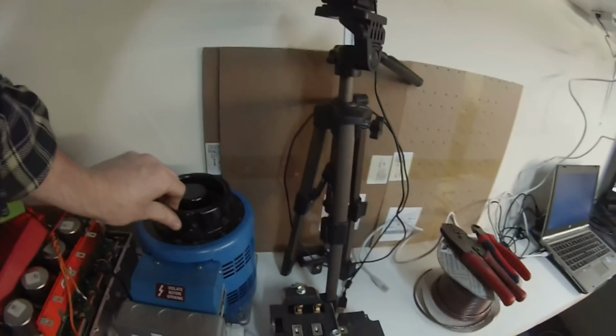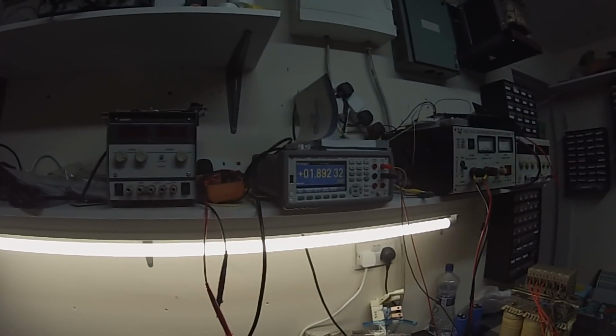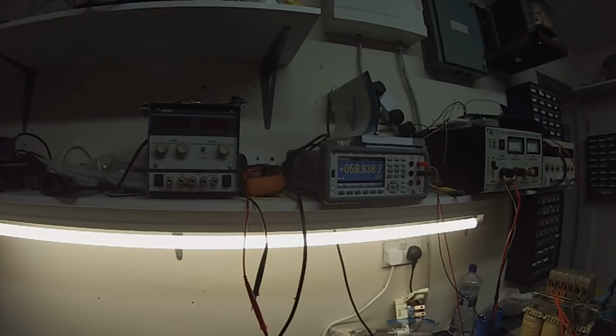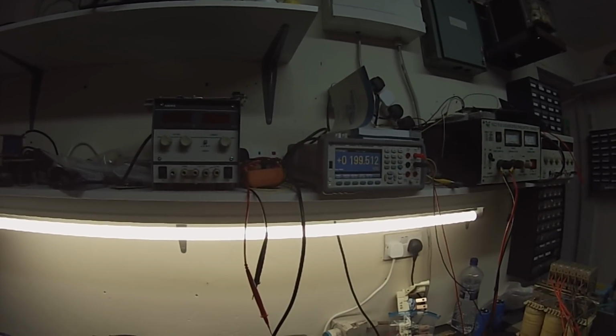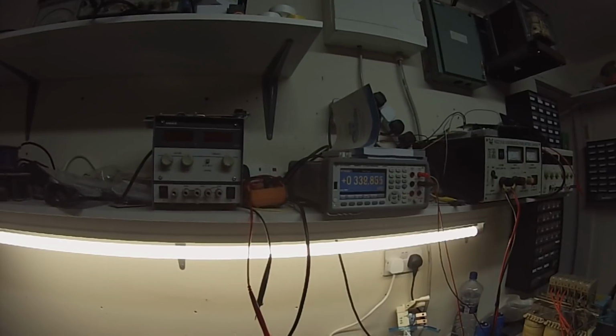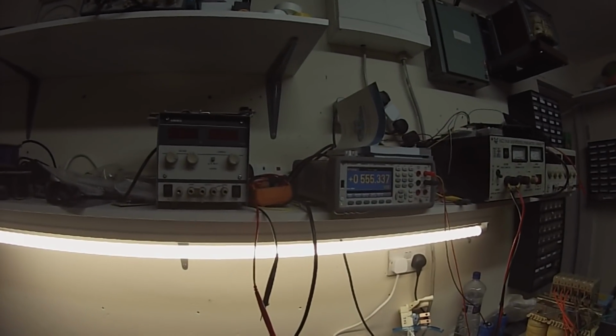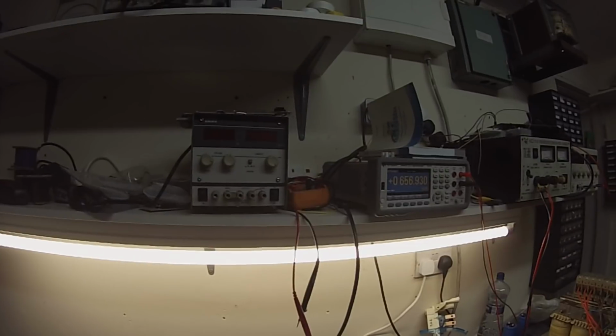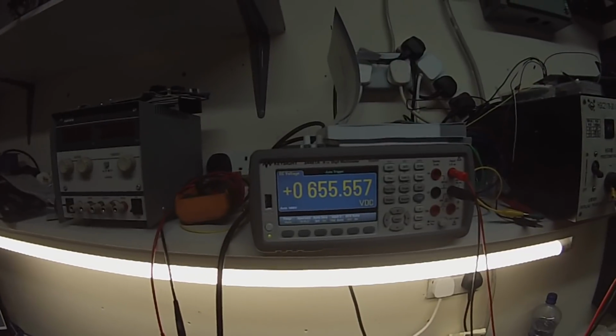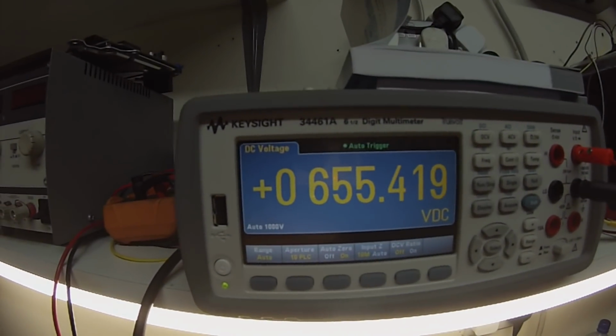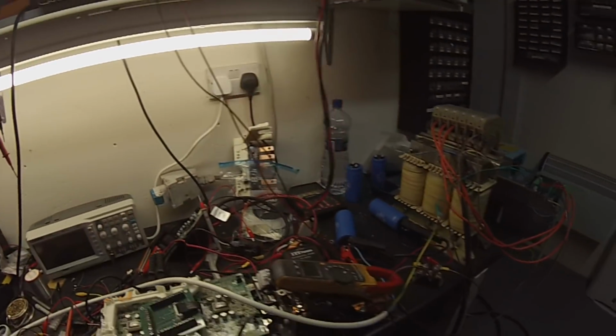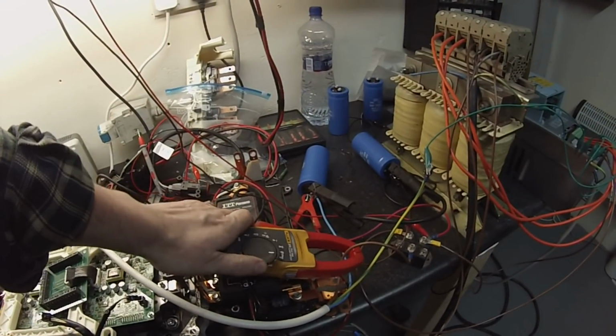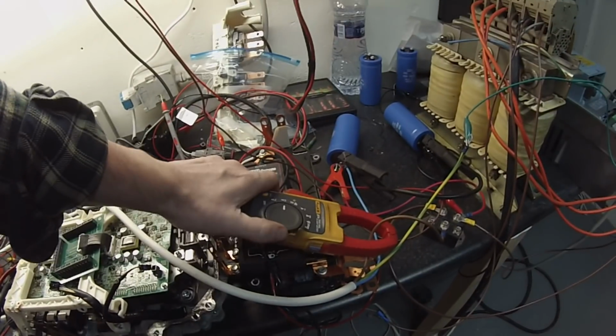What we're going to do is turn on our switch here, and I'll bring you guys over to reach around and get the Variac and increase it. Voltage is coming up, you can hear the inverter starting up. We're now at 100% on the Variac, which is 230 volts AC input, and we're getting 655 volts. Our multimeter's gone asleep, of course - fantastic design.